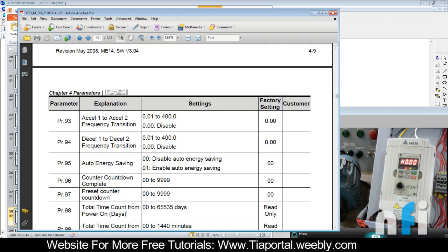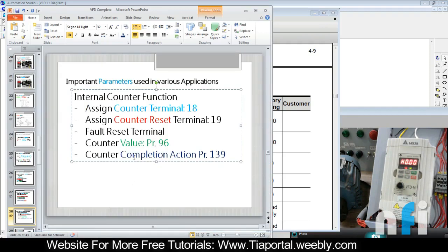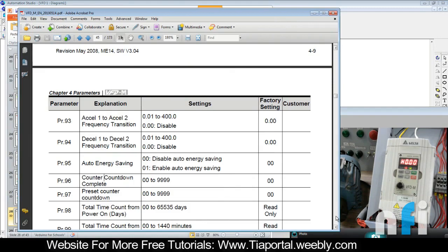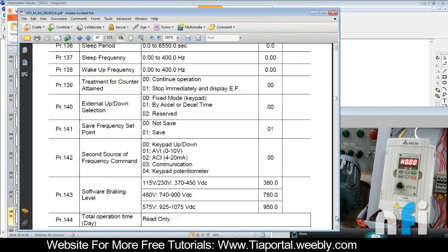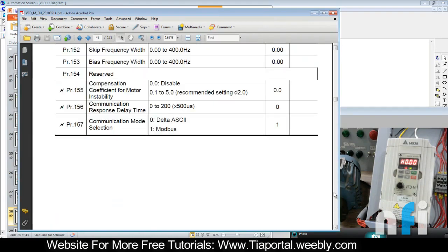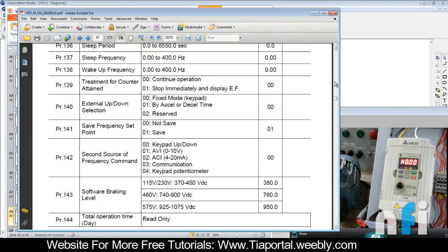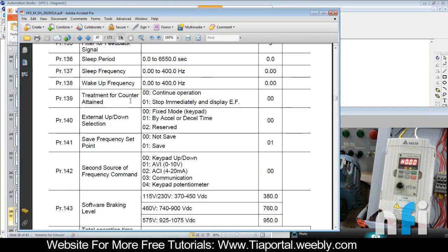Then the last parameter we need to add is counter completion action - what should happen when the counter completes its counts. It's parameter 139. Treatment for counter attain: continue operation or stop immediately and display EF.